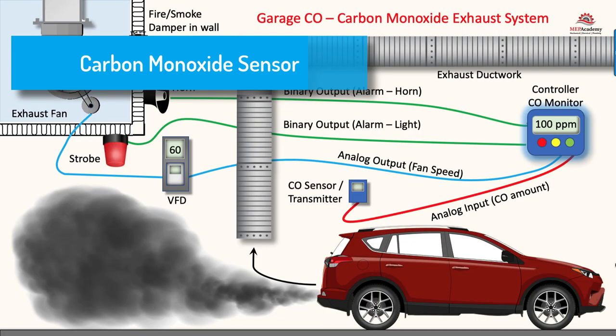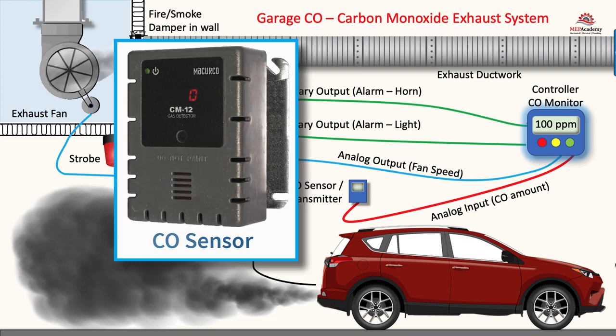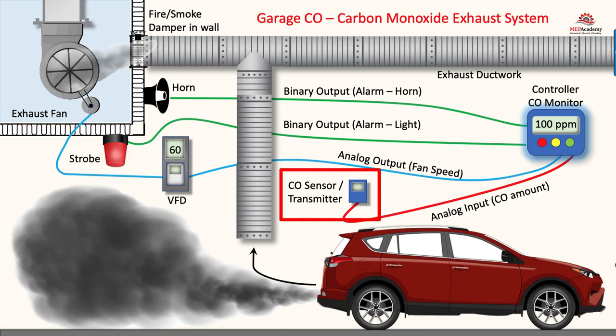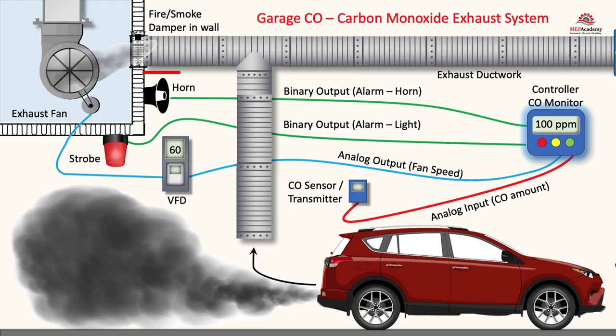Carbon monoxide sensor. Carbon monoxide CO sensors are commonly used in conjunction with garage exhaust systems to monitor the concentration of CO in the air and ensure the safety of occupants. Garage exhaust systems are designed to remove exhaust gases, including CO, from the garage space. They typically include ventilation fans or ductwork connected to the outside. The CO sensor can increase the fan speed in conjunction with a VFD when certain concentrations of carbon monoxide are reached. The activation of the exhaust system helps to reduce CO levels, providing a safer environment for occupants. When the CO concentration exceeds the threshold, the sensor can provide an audible or visible alarm to alert occupants of the hazardous conditions.